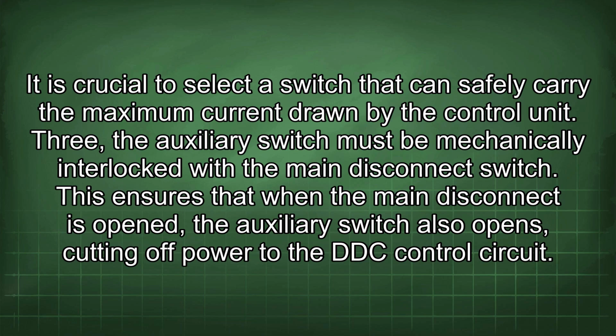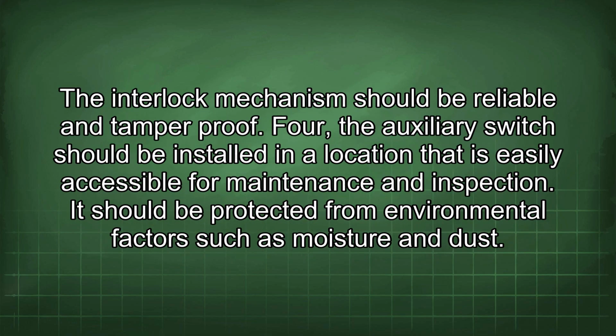3. The auxiliary switch must be mechanically interlocked with the main disconnect switch. This ensures that when the main disconnect is opened, the auxiliary switch also opens, cutting off power to the DDC control circuit. The interlock mechanism should be reliable and tamper-proof. 4. The auxiliary switch should be installed in a location that is easily accessible for maintenance and inspection. It should be protected from environmental factors such as moisture and dust.